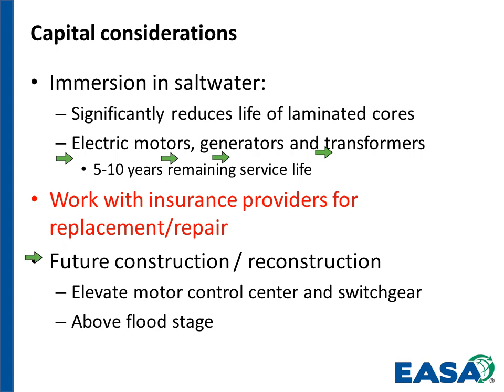Future construction, as mentioned earlier: if we can move the motor control centers and the switchgear above flood stage, that's a very simple thing to do. If we've got a room the size of a trailer, you can elevate that on stilts and put a staircase up to it. We can still concentrate our MCC so that all the switchgear and so on is together for testing purposes, for cleaning purposes, for the ability to air condition the room and climate control it to keep the operating temperature. However, if you build that stuff above the flood stage, you won't be in the same boat as you are in this failure, or perhaps were in the previous failure.